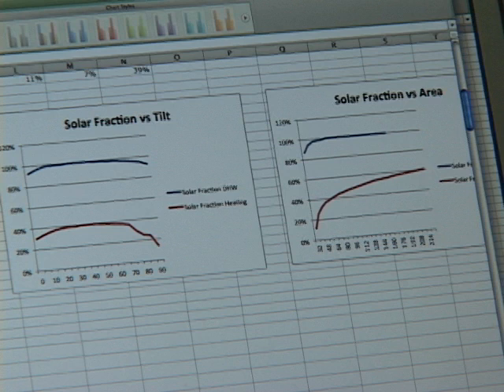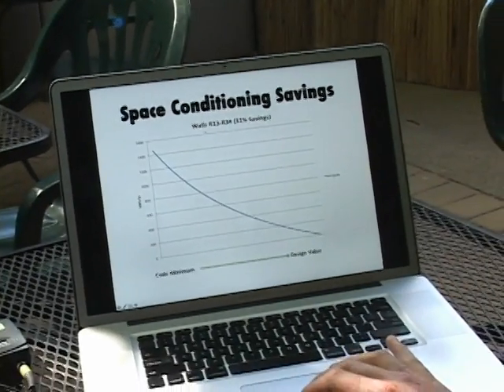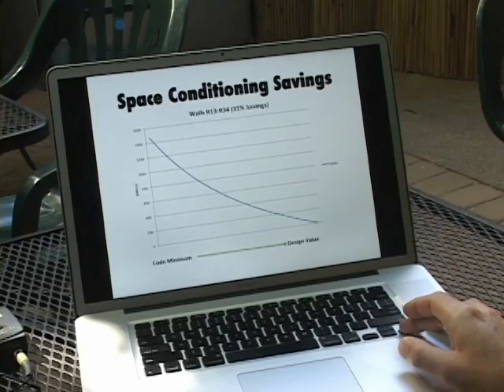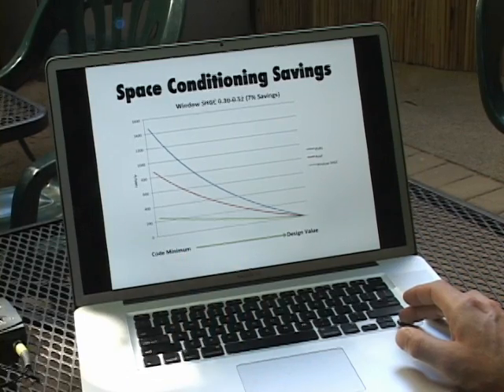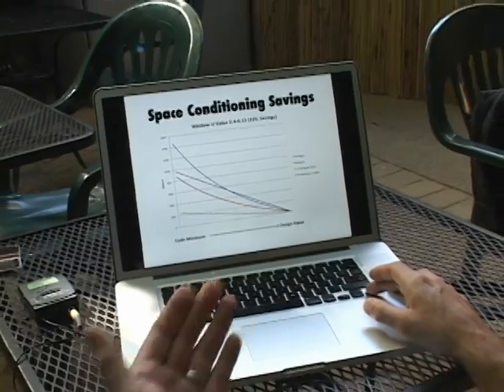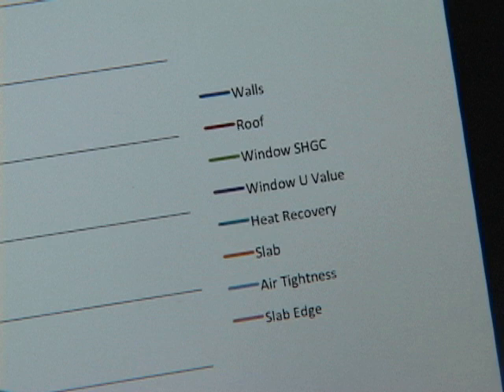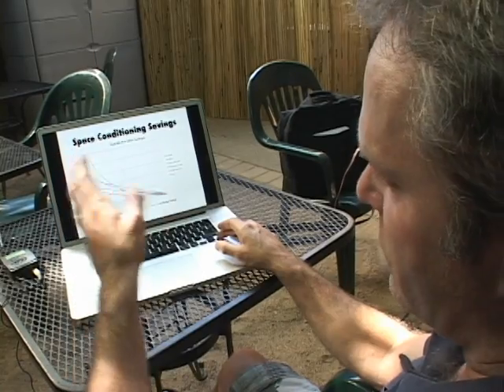So a major difference just from that air tightness. Over here I'm also seeing what I can do for solar fraction in the building, and I get a whole lot less out of it with an inefficient building than I do with an efficient one. This is using results from PHPP to show the reduction in heating and cooling demand based on going from code minimum to our final design value. For the walls we went from R13 to R34 — a 31 percent reduction. The roof went from R30 to R60 — 21 percent savings. The window solar heat gain coefficient went from 0.3 up to 0.52 — 7 percent savings. The U-value from 0.4 down to 0.15 — 22 percent savings. Heat recovery from 0 percent up to 83 percent — 27 percent savings.